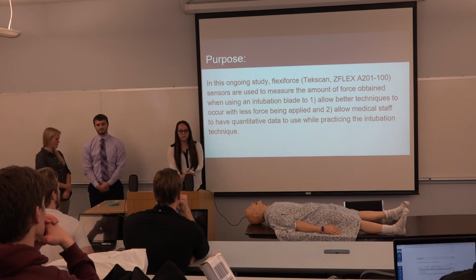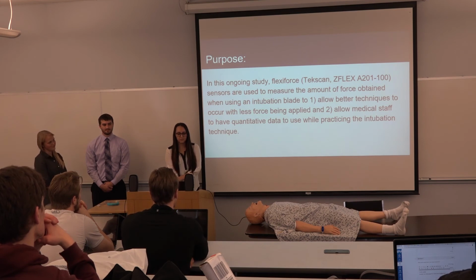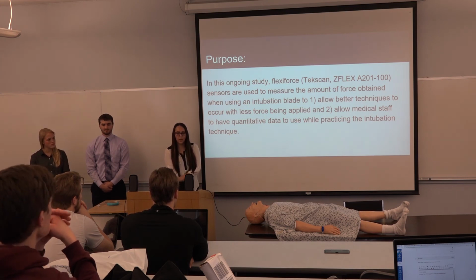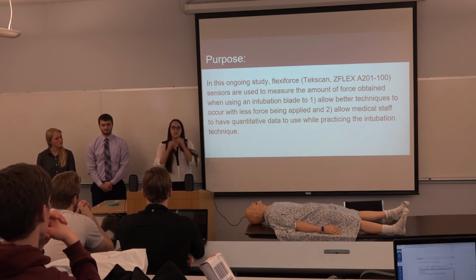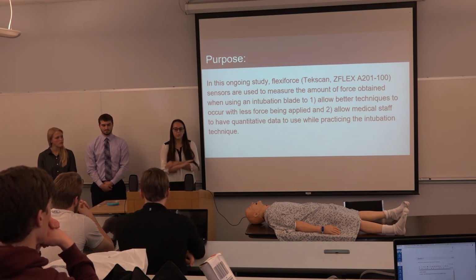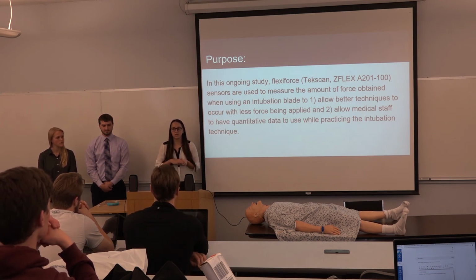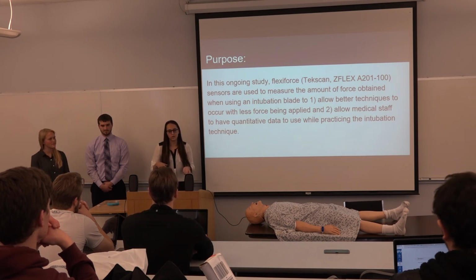Our purpose is, in this ongoing study, FlexiForce sensors are used to measure the amount of force obtained when using an intubation blade to, 1, allow better technique to occur with less force being applied, and 2, allow medical staff to have quantitative data to use while practicing the intubation technique. We found in our pre-research that there wasn't any quantitative data. There's some qualitative data, but nothing showing the pressures that are currently being used, what's a safe amount of pressure to use, and what's excessive and is going to hurt the patient.